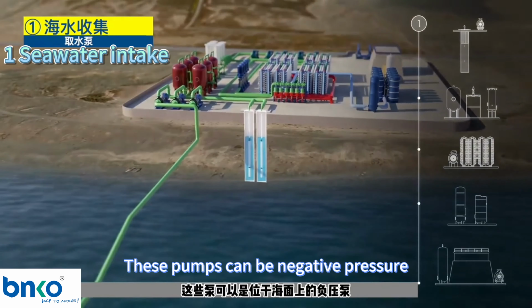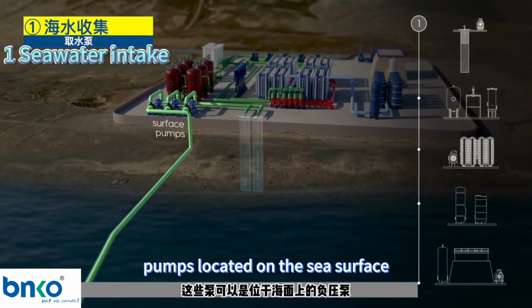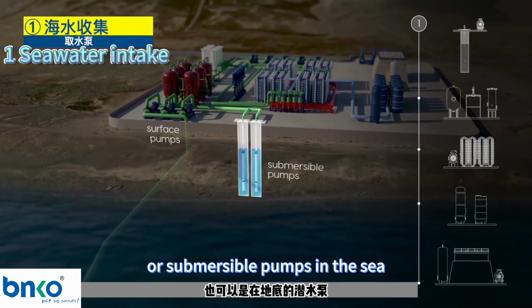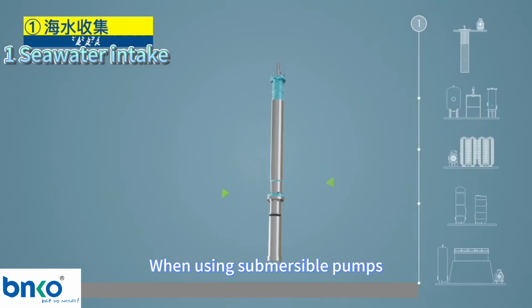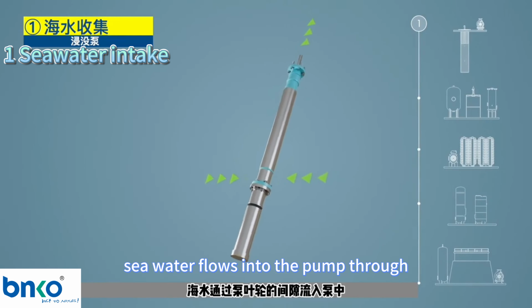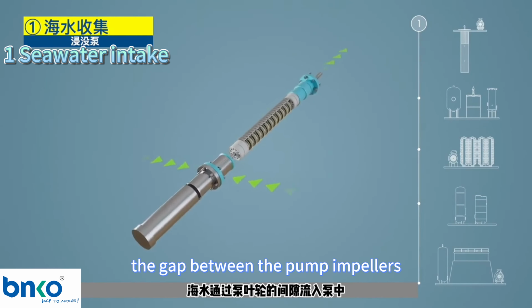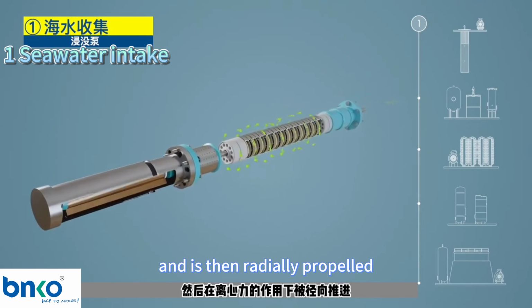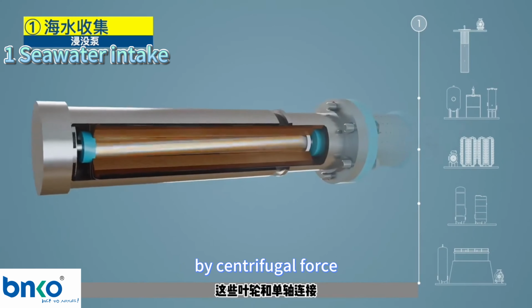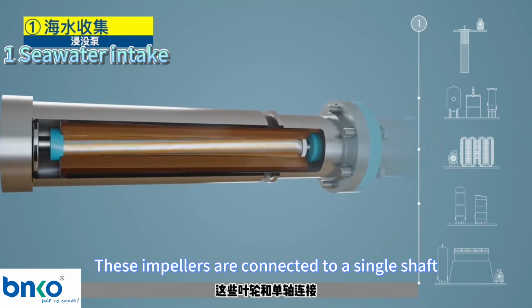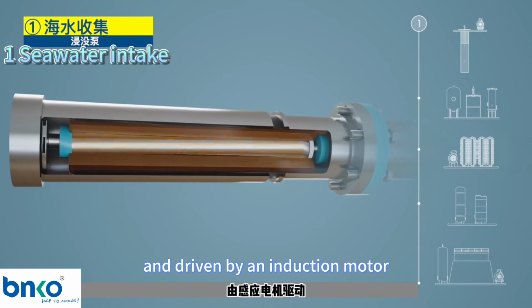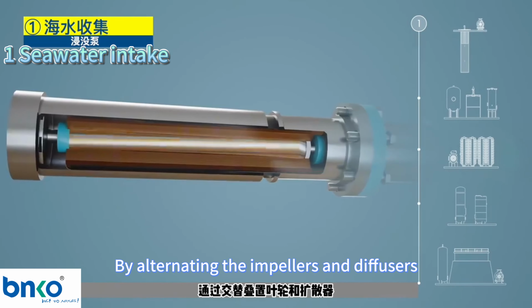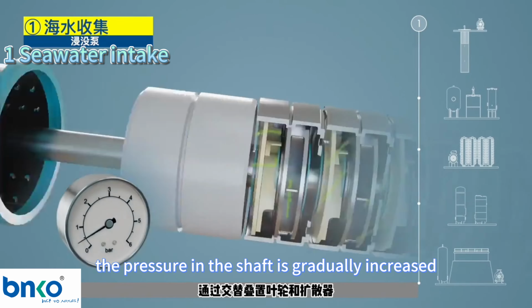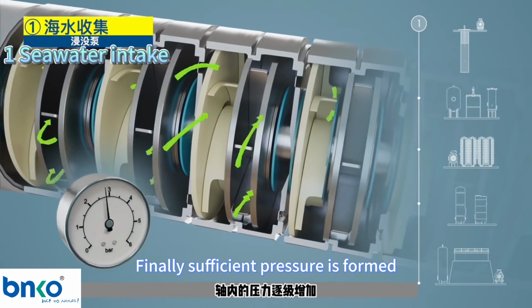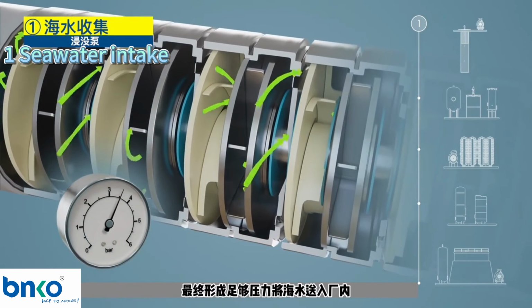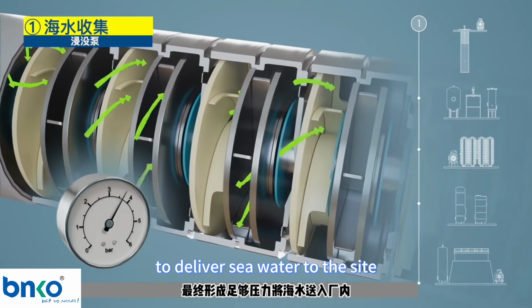These pumps can be negative pressure pumps located on the sea surface, or submersible pumps in the sea. When using submersible pumps, seawater flows into the pump through the gap between the pump impellers, and is then radially propelled by centrifugal force. These impellers are connected to a single shaft and driven by an induction motor. By alternating the impellers and diffusers, the pressure in the shaft is gradually increased. Finally, sufficient pressure is formed to deliver seawater to the site.